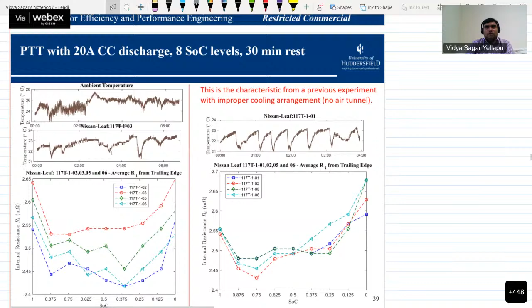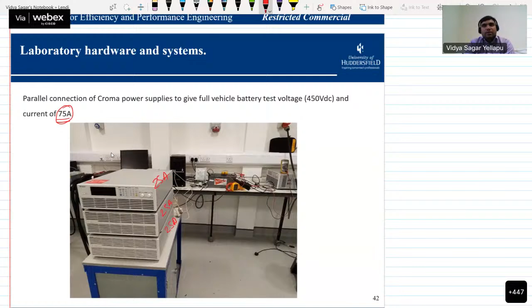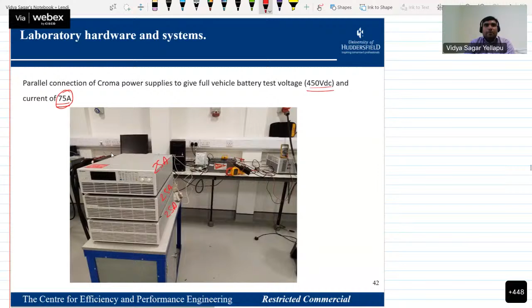So all these are different average resistances for different modules. To the laboratory hardware and systems. So this is the power supplies connected in parallel combination to increase the current rating. Each power supply is capable of giving 25 amperes, to increase the discharge current and to increase the charging current to some higher value so that the charging finishes quickly. All these are connected in parallel operation. So they could give 75 amperes in this connection, and the battery test voltage is 450 volts.